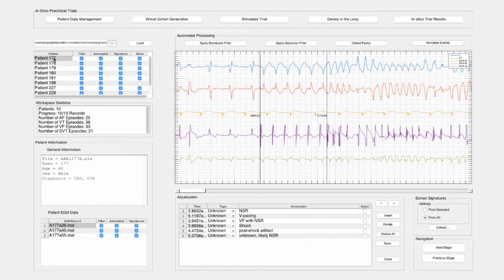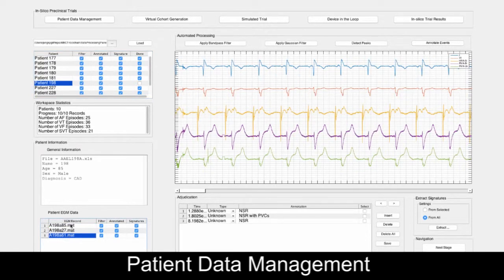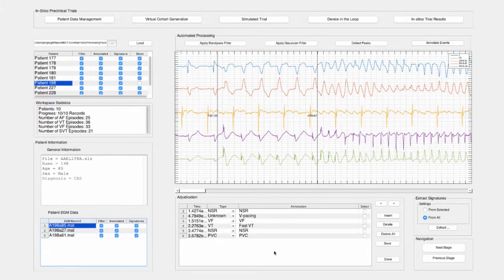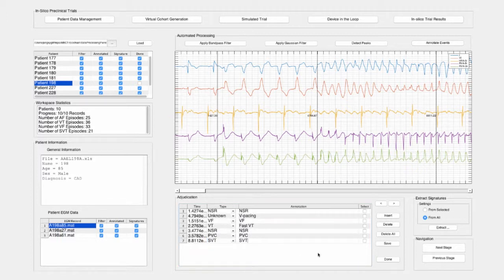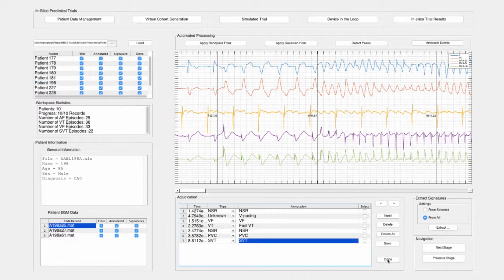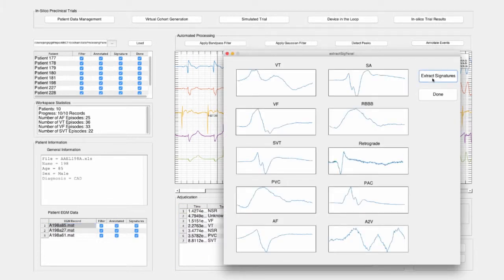Now we will demonstrate how to run an in-silico preclinical trial with our toolchain. An in-silico preclinical trial consists of five different steps. In the first step, real patient data needs to be processed to identify clinical conditions and device interactions. After importing a patient record containing recorded electrogram signals, the raw data signals are manually adjudicated by clinicians and automatically filtered to remove noise artifacts and then labeled. Within a record, the different patient conditions, known as arrhythmias, are annotated to extract patient signatures.